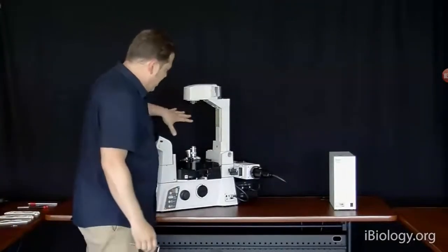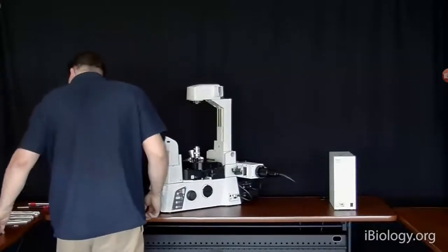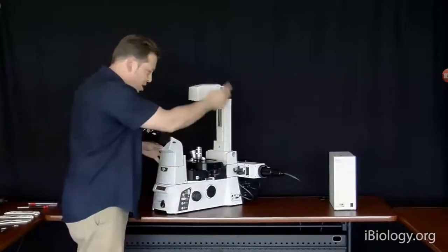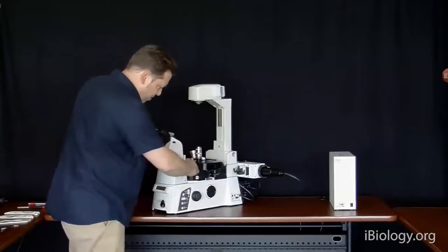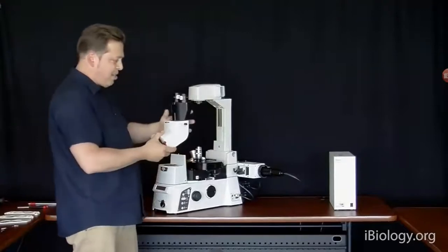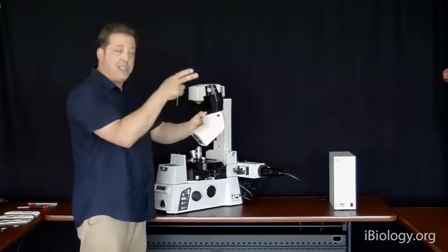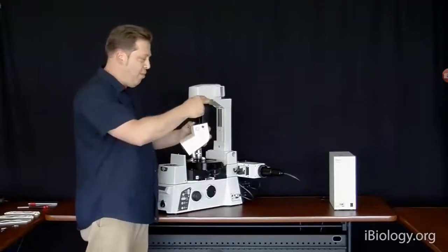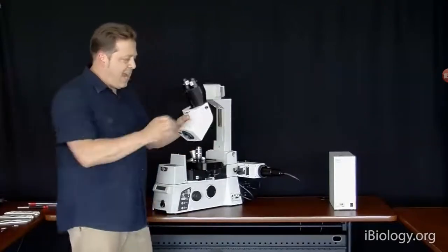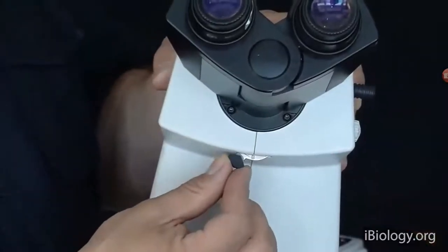So now we're really getting down to sort of the base of the microscope. I'm going to take off next the eyepieces of the microscope, and then we'll get back to the light path through. This is what we call the head of the microscope. And basically, it's a set of prisms that splits light to the eyepieces so you can look in the microscope. And there's really nothing too special about it, other than it's got what's called a Bertrand lens that can be in an open position or a Bertrand position.